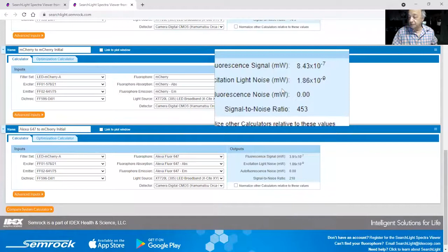And to find that, I select the filters to correspond to the M-Cherry set. The fluorophore corresponds to M-Cherry fluorophore, and then we have, of course, the light source and the detector. And then we have some kind of quality indicator here, which is the fluorescence signal level. That is sort of a small number. I can perhaps show you what it is, 8.4 times 10 to the minus 7 milliwatts. And then the calculator below it shows what happens if you use Alexa 647 as the fluorophore instead of M-Cherry. That tells you how much bleed through you get of that. And in fact, 3.9 or so compared to 8.4, it's a very significant amount of bleed through.